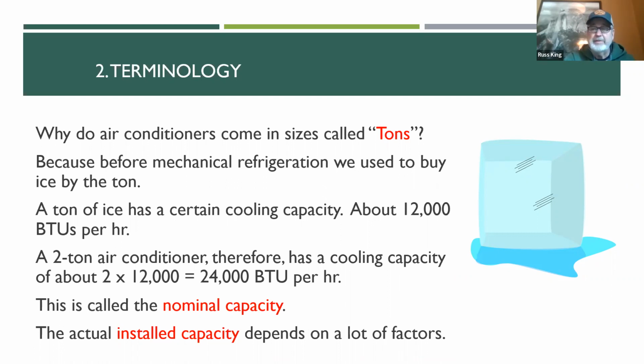There's another capacity that's even more important, and that's the installed capacity. The actual cooling capacity of an air conditioner is different depending on where it's installed. So an air conditioner in Las Vegas will actually give you a lot less cooling than an air conditioner in, say, San Jose, okay? Because of the outdoor temperature. So installed capacity is very important to understand. Nominal capacity is just what we call it, right?